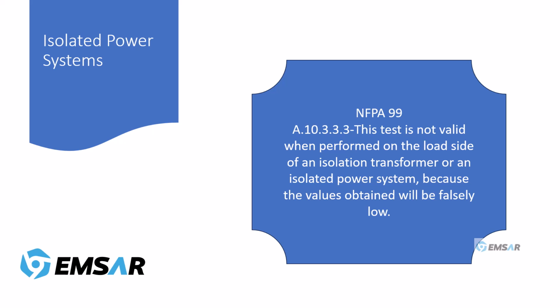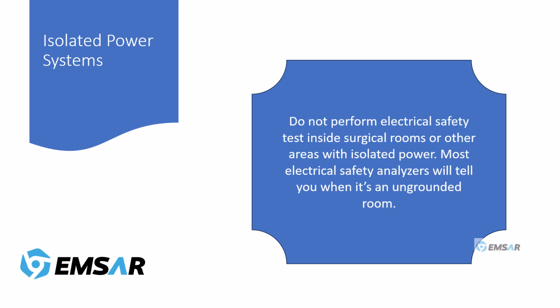And most of your safety analyzers will tell you when you're in an ungrounded outlet. But once again, do not perform electrical safety tests inside surgical rooms or other areas with isolated power. Most electrical safety analyzers will tell you when the room is ungrounded.